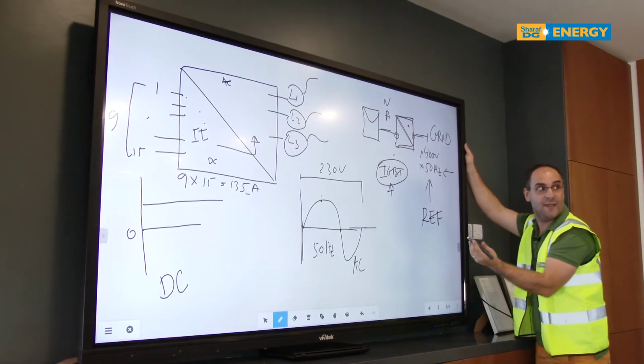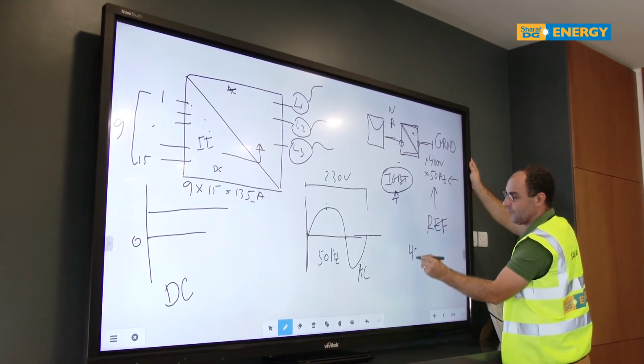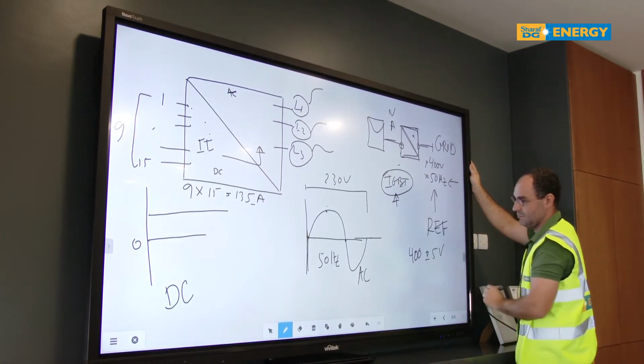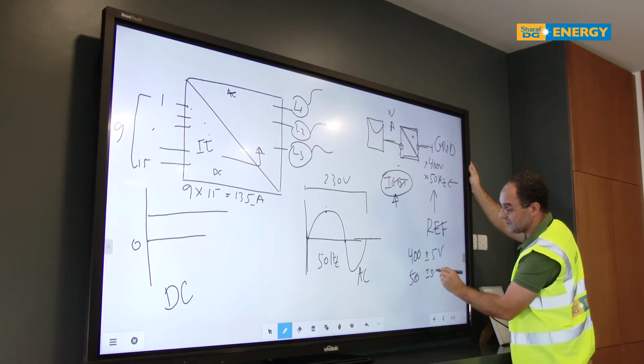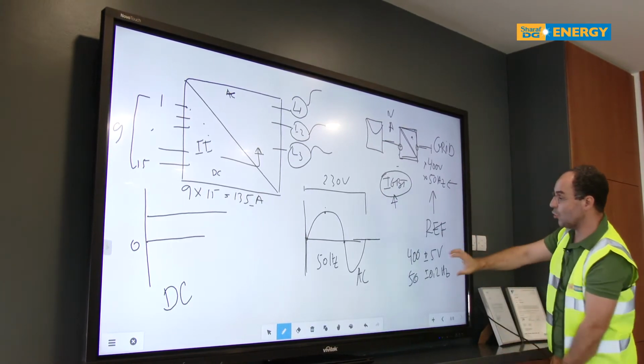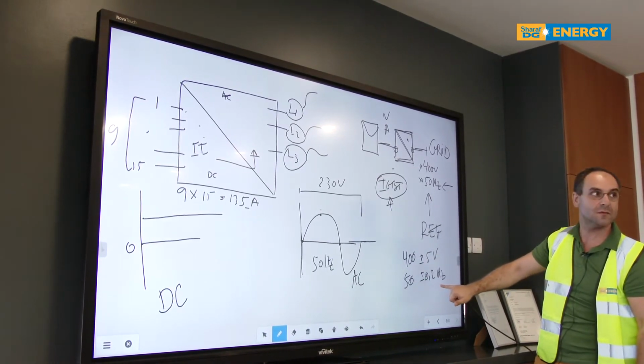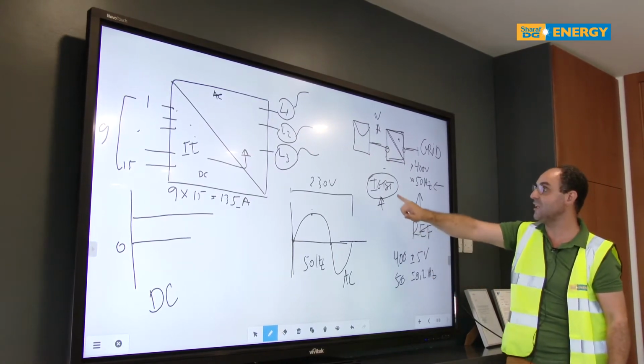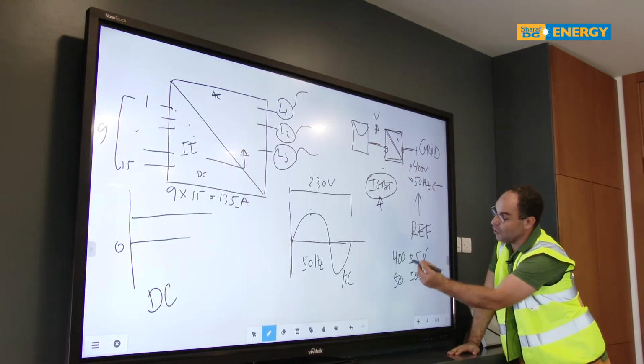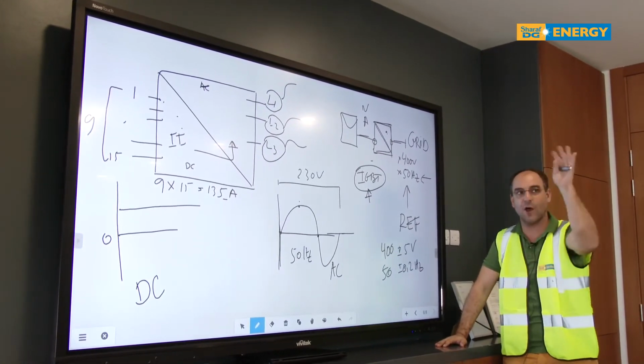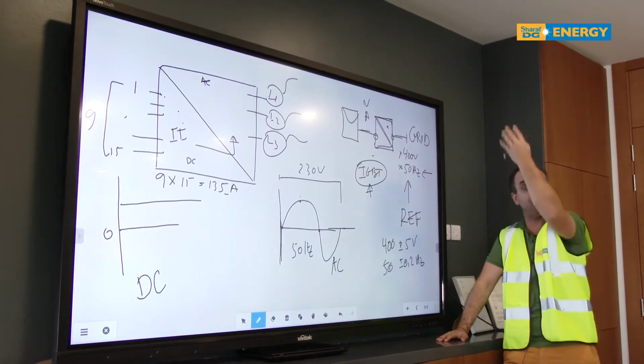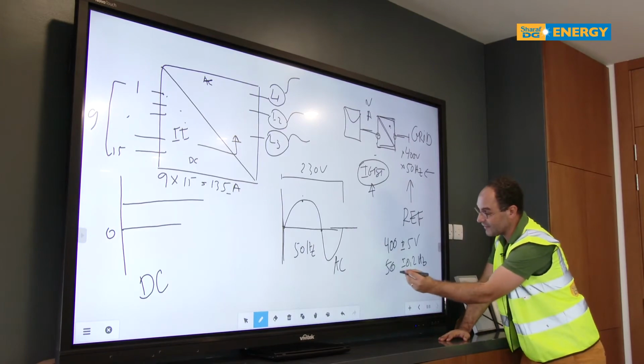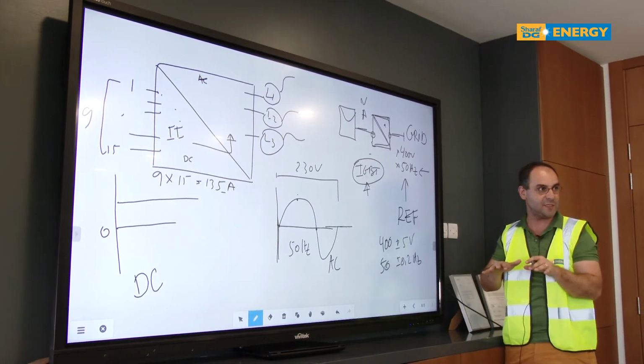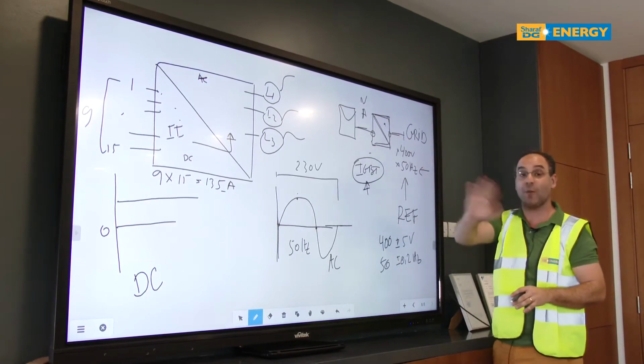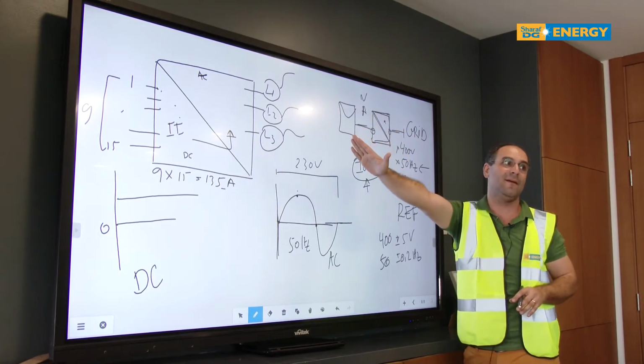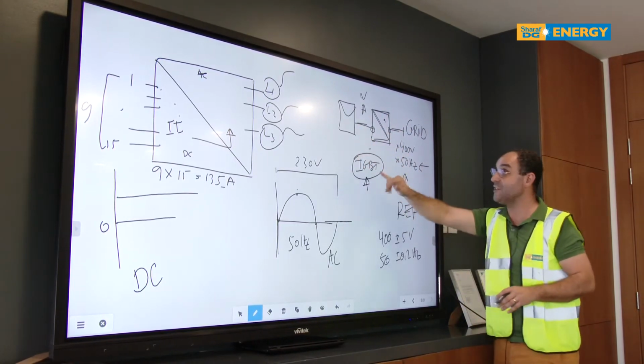So the reference is this. The machine knows that it can go, for example, 400 volts plus or minus 5 volts, and the frequency can be much tighter, let's say plus or minus 0.2 hertz. Until your grid jumps out to 55 hertz, the IGBT will not do anything. So if, at a certain moment, your neighbors are off and ramping up, the load changes the voltage to the power plant and the frequency comes back at 50.2, your system will remain the same. But if that frequency comes to 53, this guy will say stop everything, isolate from here back. So the IGBT protects that.